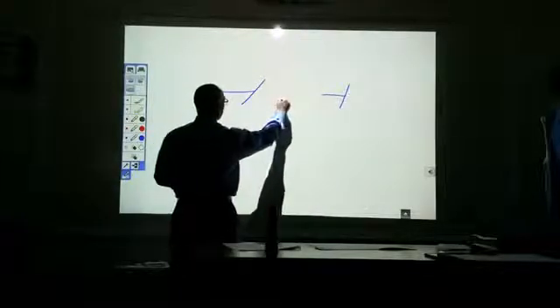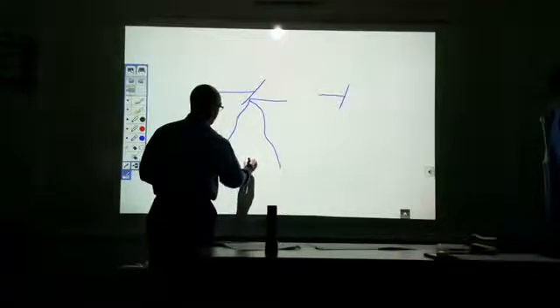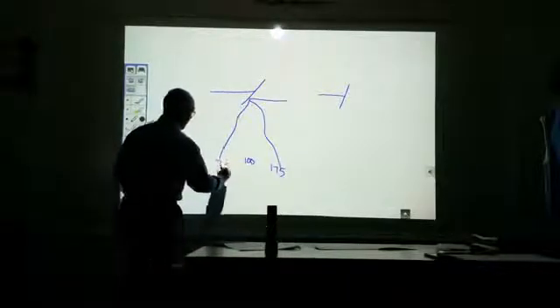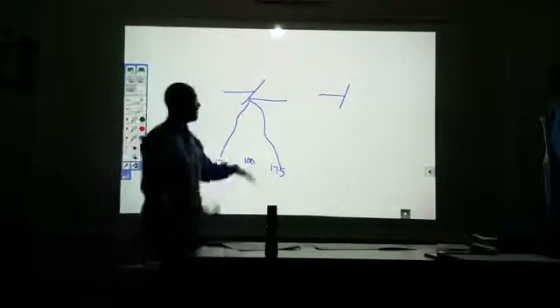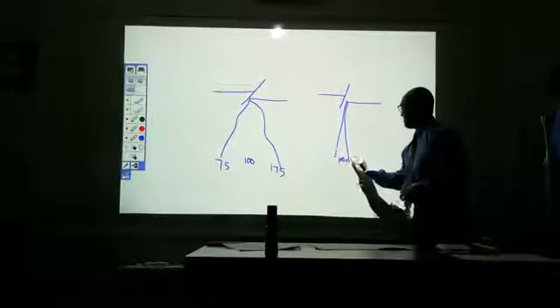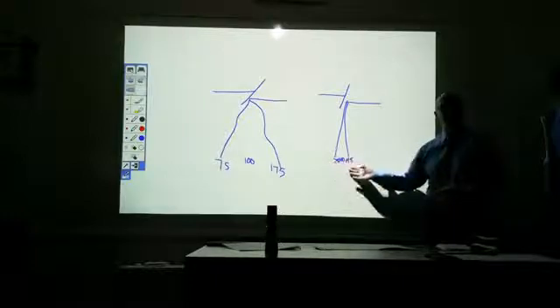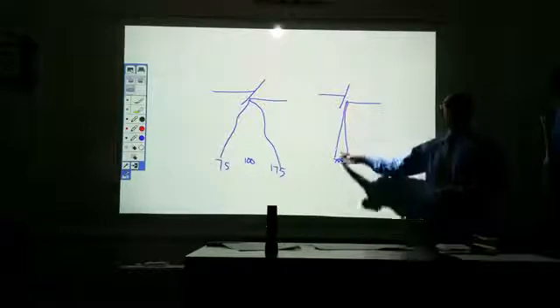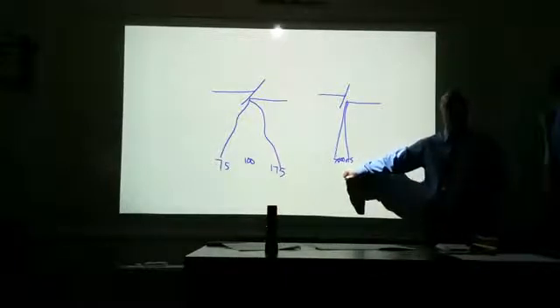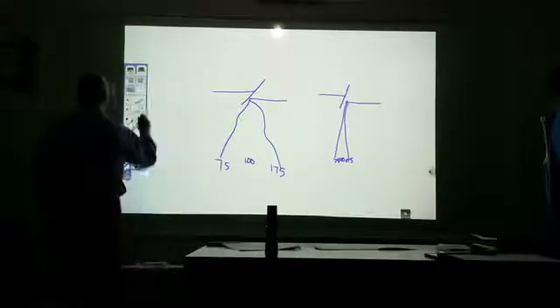What does that mean? With a greater angle, as the beam interacts, it's going to be wider. Your central ray is in the middle, with greater intensity on the cathode side — let's call it 175 — and weaker on the anode side, about 75. It's gradual. But with steeper, smaller angles, the beam is tighter. The transition from 175 to 75 is not gradual — it's more obvious and more abrupt. So with steeper anode angles, the anode heel effect is more apparent.